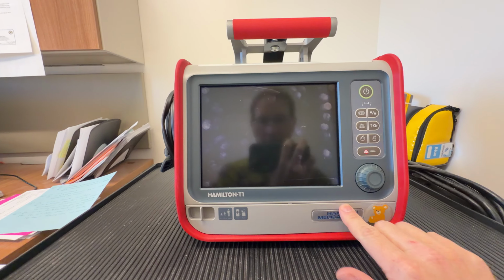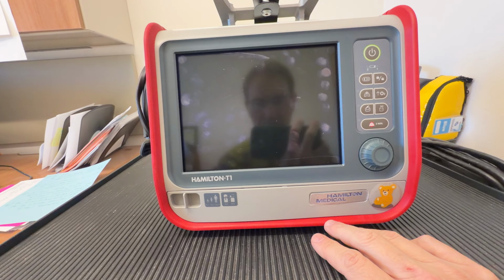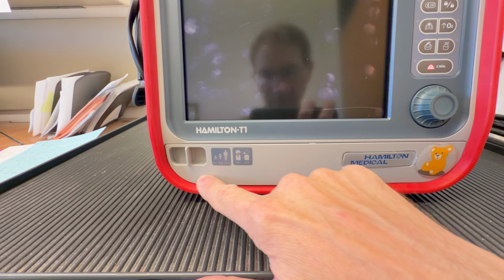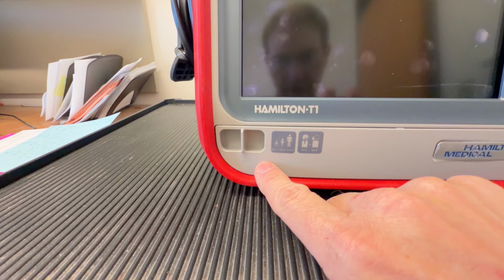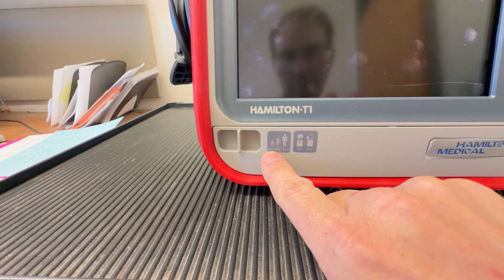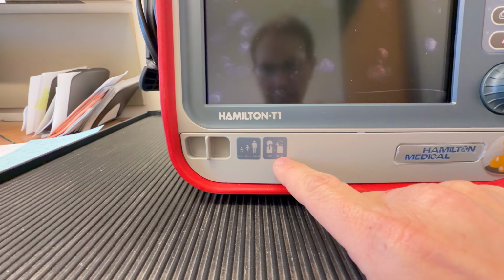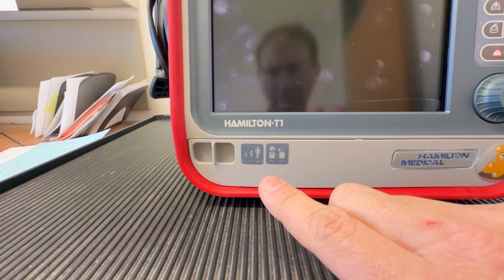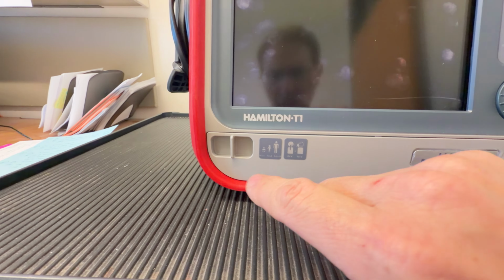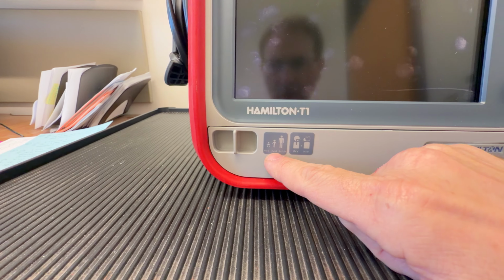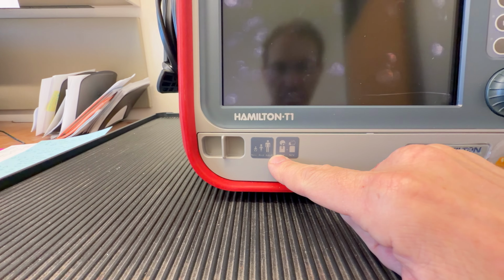This is a front battery cover here. On this cover, you're going to see some little icons down here that tell you what the ventilator is capable of doing, and if there are any special modes or settings that the ventilator is capable of. You'd have a little tag here so you can see this is capable of providing mechanical ventilation to neonatal, pediatric and adult patients, both invasive ventilation and non-invasive ventilation. Now you do need a specialized vent circuit for neonatal patients. So for this particular series of videos, I'm going to focus on the pediatric and adult patient setup and making changes.